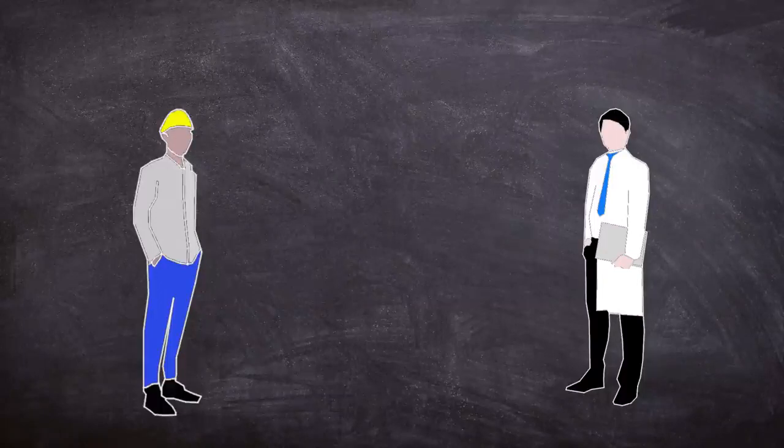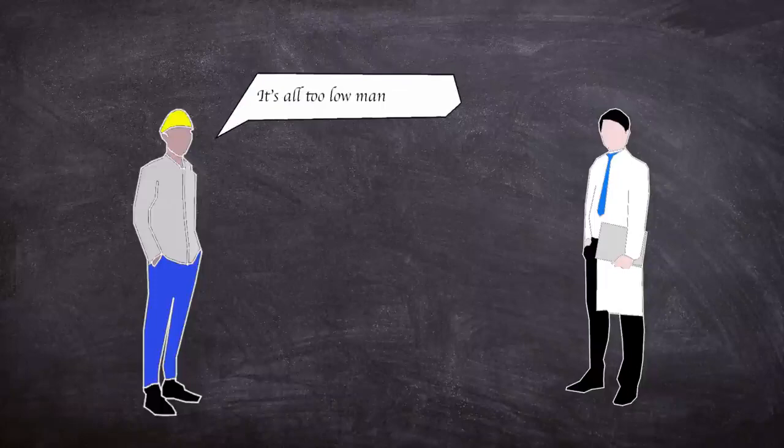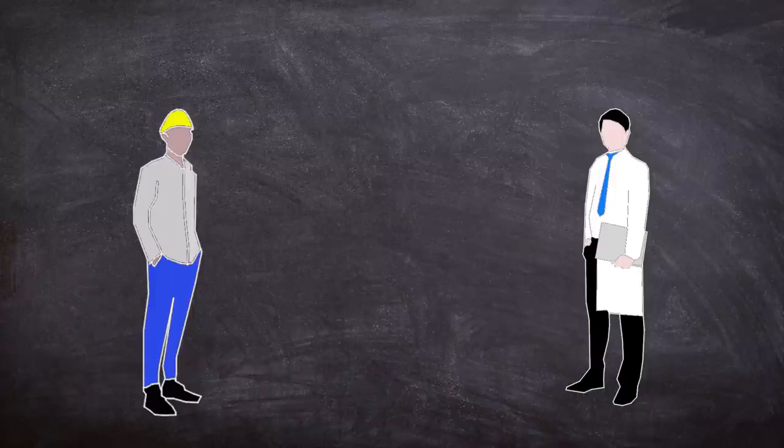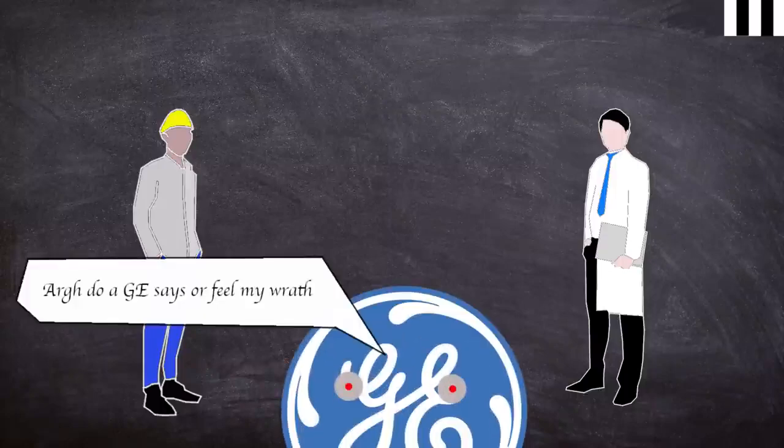Issues were raised by some engineers during construction, as placement of safety critical equipment below grade had higher flood risk, especially with the lower bluff height. However, these issues were swept away by TEPCO's decision to follow GE's design plans to the letter. And oh boy, that would come back to bite them.